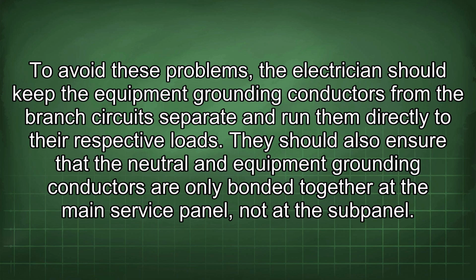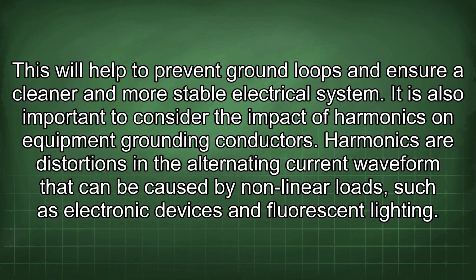To avoid these problems, the electrician should keep the equipment grounding conductors from the branch circuits separate and run them directly to their respective loads. They should also ensure that the neutral and equipment grounding conductors are only bonded together at the main service panel, not at the subpanel. This will help to prevent ground loops and ensure a cleaner and more stable electrical system.